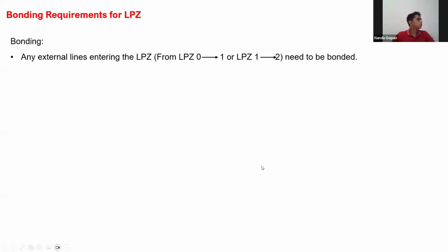Next, bonding requirements. Just take a pen. Any external line entering LPZ 0 to 1 or LPZ 1 to 2 should be bonded. By lines I mean any power line or telecommunication line should be bonded via an SPD. If there is any pipeline, cable tray, or HVAC system entering, that should also be bonded. The metal component should be bonded if it is entering from zone 0 to zone 1, zone 1 to zone 2, or zone 2 to zone 3. Whenever there is entry from one zone to another, you are supposed to 100% bond it.